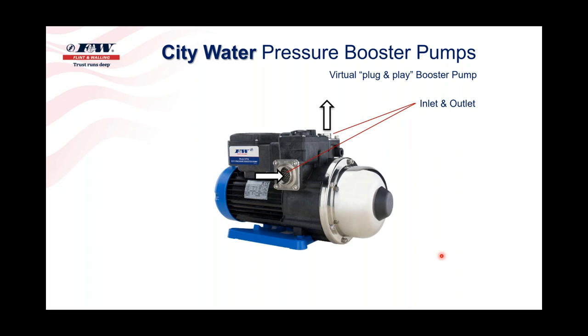These are 1-inch stainless steel flanges. There's a flow switch in there, so this pump operates off its own flow switch. You have to have a demand of water that is at or above 7/10 of a gallon per minute in order for that flow switch to activate. It's got a little storage tank built up front with a little air charge in it. I mentioned this is a plug and play. Everything's integral to this pump itself.